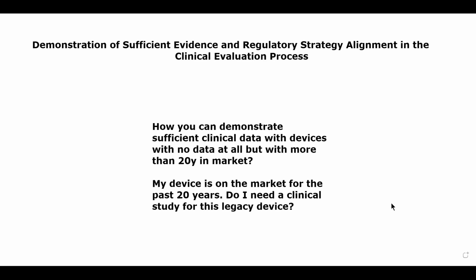Sure. I'm going to answer the second one first. And we did kind of cover this in the presentation, but you'd need a clinical study for your legacy device if changes have occurred due to the MDR regulations or in the therapeutic landscape as identified by state of the art that would impact your device or the therapeutic options for your generic device category.